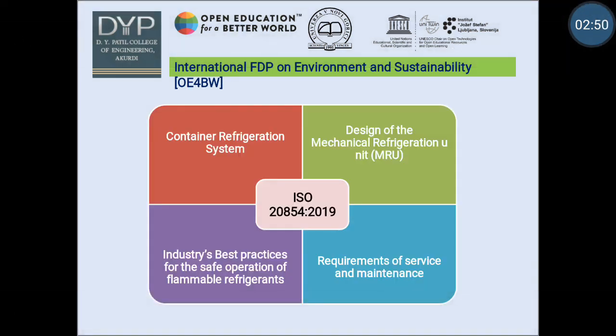Let's see the first ISO standard, ISO 20854-2019. The scope of this standard is limited to container refrigerating systems operated in conjunction with the carriage of refrigerated cargo. This document describes the design of mechanical refrigeration units and operation of container refrigerating systems in all anticipated operational modes and locations. It also describes the industry's best practices for safe operation of flammable refrigerants and requirements for service and maintenance when working with flammable refrigerants.